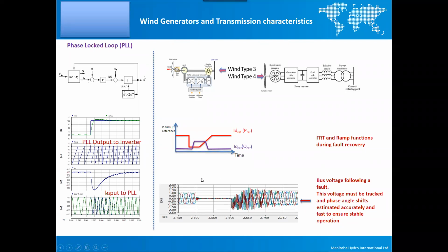The real fact is, in real life, you don't get sinusoidal voltages all the time. When you have a fault in your system and the system is recovering from a fault, the voltages could look nasty, messy, filled with harmonics like this. But yet, if you want to meet grid codes and stay connected, the so-called fault ride-through requirements of wind connections, the converter control should track the angle, the 0 to 360 variation of the fundamental component of this garbage waveform, accurately. Otherwise, the controls will mess up, firing won't be as expected, and you will see wind farms trip.